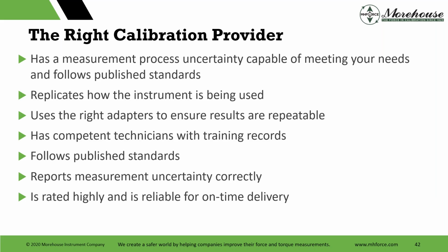So, talking about calibration, some things you may want to know about a calibration provider: has measurement process uncertainty capable of meeting your needs and follows published standards. They replicate how the instruments are being used. They use the right adapters to ensure results are repeatable, have competent technicians with training records, follow those published standards, report measurement uncertainty correctly, and are highly rated for on-time delivery. Things you want to know.